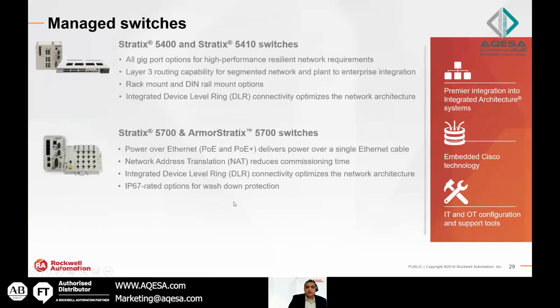If we need more than this, we go to the 5700 and Armor Stratix 5700, where you have Power over Ethernet, NAT (network address translation), integrated device level ring, and some catalog numbers, and again you can have up to IP67. This one has a maximum of 2 giga ports, 1 giga ports, even if you have 4 fiber, 2 of them are 1 giga. But if you need all giga, all fiber, up to 20 ports per module per switch, we go to Stratix 5400.